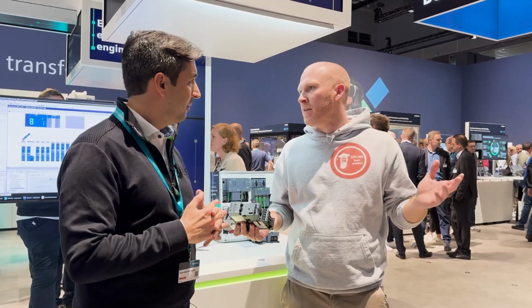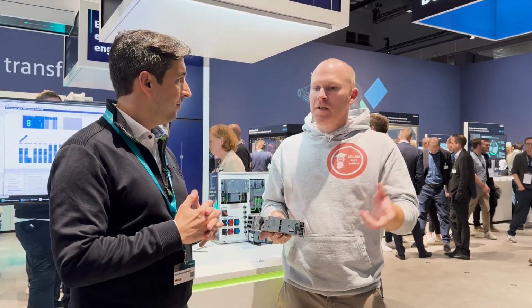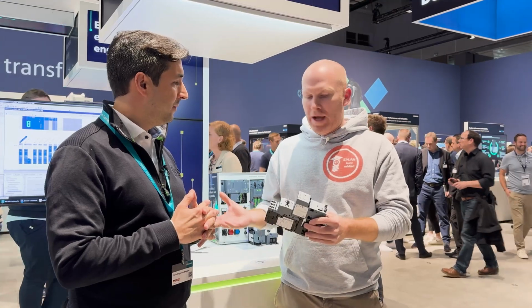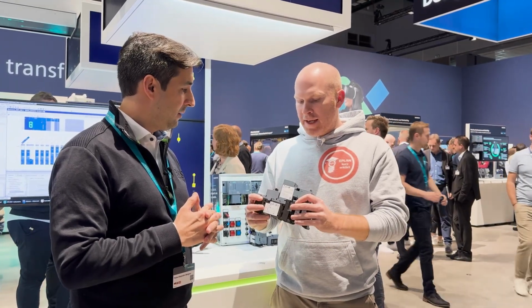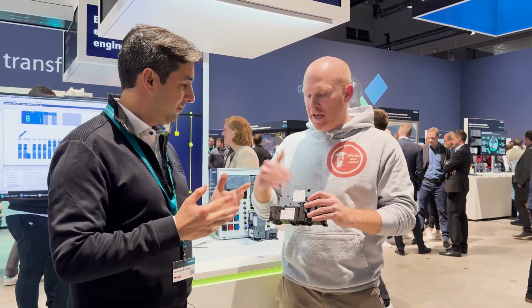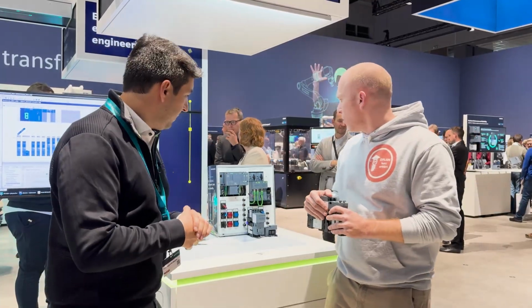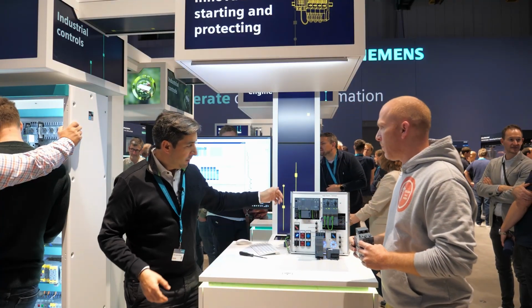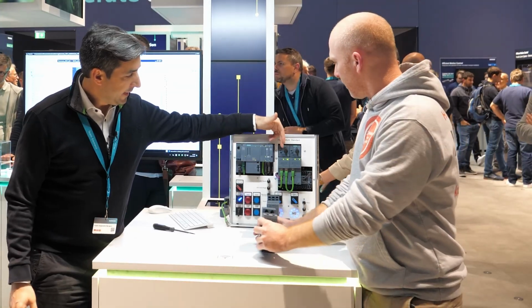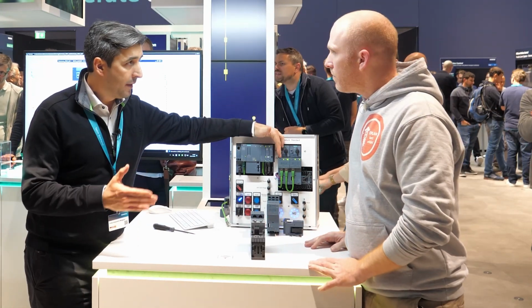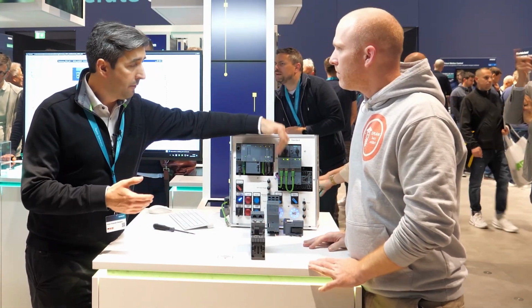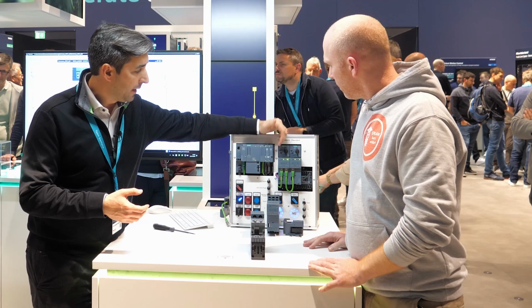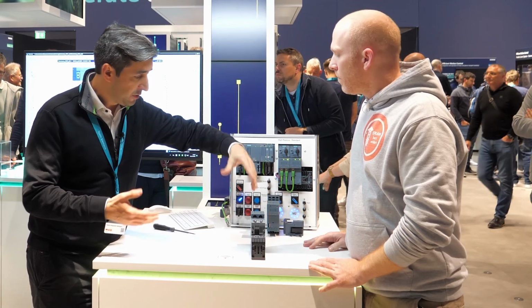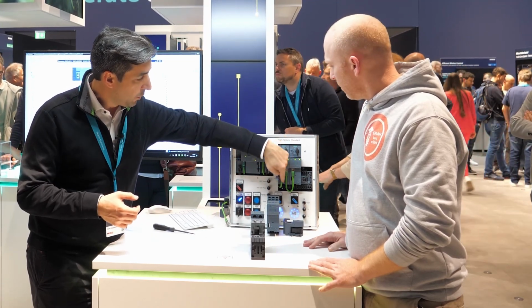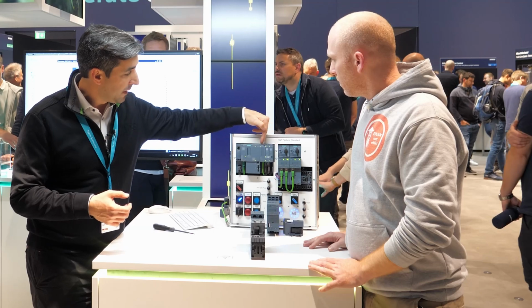Yeah, predictive maintenance is an important topic, but let's start one step earlier about the wiring, because what I can see, wiring is not necessary to energize the contactor anymore. Yeah. And how do you connect? Well, maybe you can explain it here on this example. Yeah, basically you just don't need anymore this input and output that normally you need for the contactor and to have the circuit breaker. You just connect this module like I showed before, and you go with this communication extension rack from the ET200.